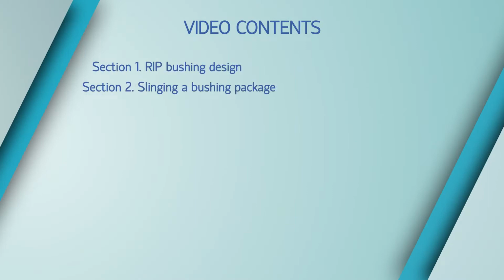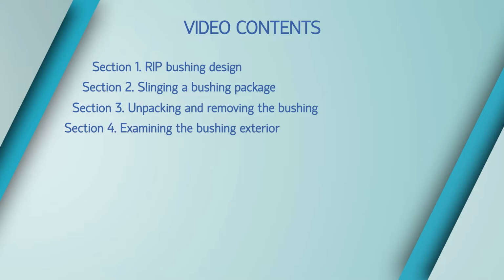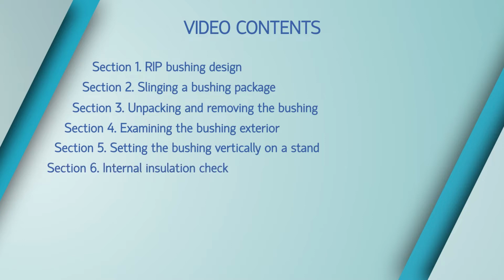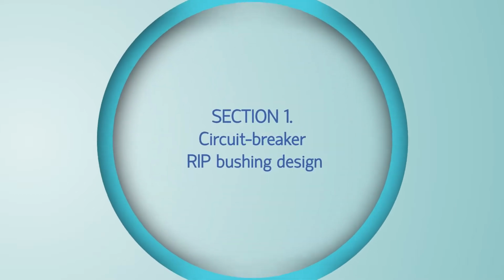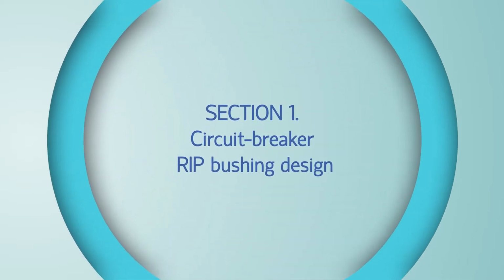Video contents: RIP bushing design, slinging a bushing package, unpacking and removing the bushing, examining the bushing exterior, setting the bushing vertically on a stand, internal insulation check, installing the bushing on a circuit breaker, post-installation tests. Conclusion: circuit breaker RIP bushing design.